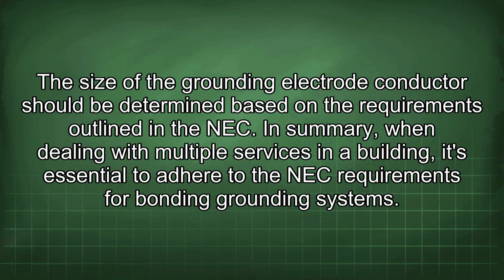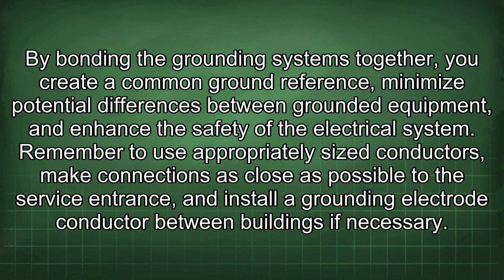In summary, when dealing with multiple services in a building, it's essential to adhere to the NEC requirements for bonding grounding systems. By bonding the grounding systems together, you create a common ground reference, minimize potential differences between grounded equipment, and enhance the safety of the electrical system. Remember to use appropriately sized conductors, make connections as close as possible to the service entrance, and install a grounding electrode conductor between buildings if necessary.